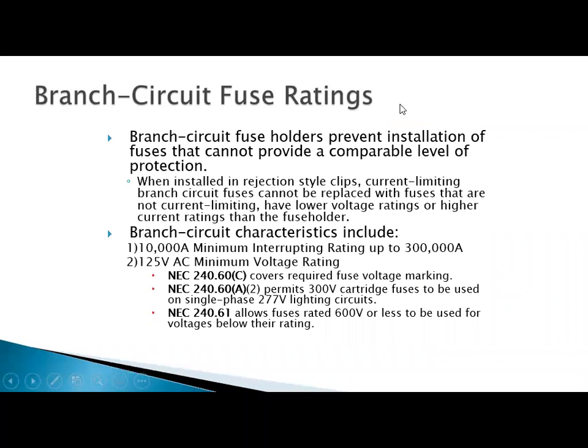So some fuse ratings, and this would be all in Article 240 of the National Electrical Code. These standard fuses can be anywhere from 1 amp all the way up to 6,000 amps. And then they can have different interrupting ratings, right? They can be down as low as 10,000 or up to 300,000. So remember that the interrupting rating is the amount of fault current that it can safely interrupt. Article 240 is also going to tell us that Edison-based fuses have to be non-tamperable.